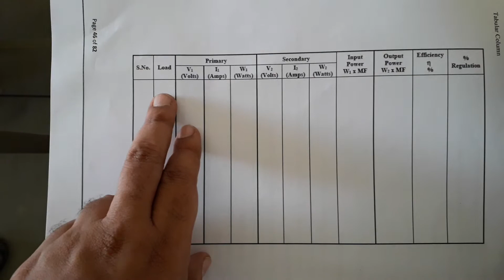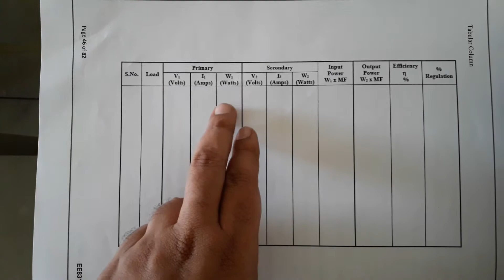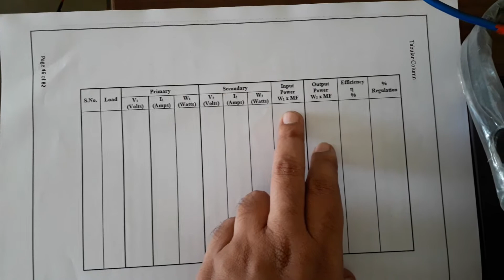See here, it is the serial number, and the load, the primary side V1, I1 and wattmeter reading in watts. Similarly, note down the secondary side voltmeter reading, ammeter reading and wattmeter reading. After that, using the wattmeter readings, you have to calculate the input power, the amount of power we feed to the primary side, and the amount of power we get across the secondary side load. Then you know the formula of efficiency is output power divided by input power, and using the regulation formula you can calculate the percentage regulation.